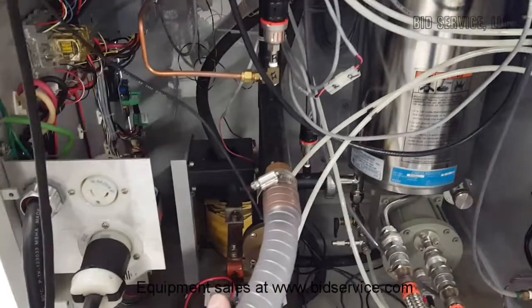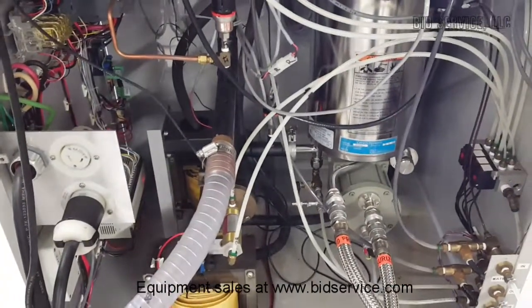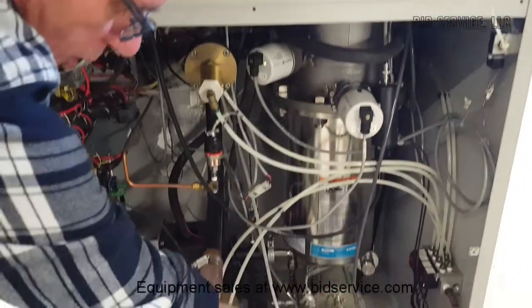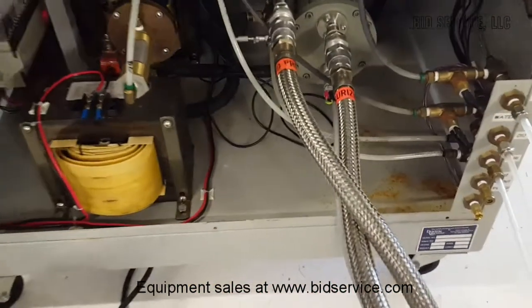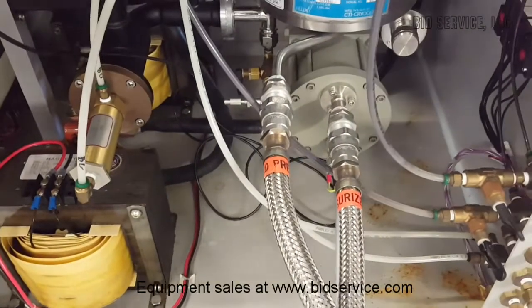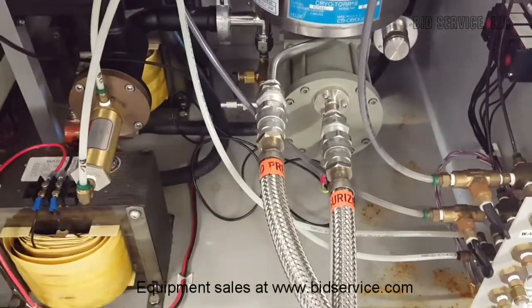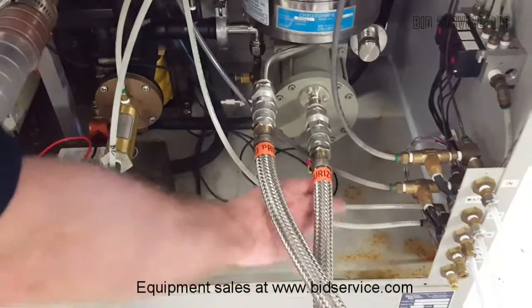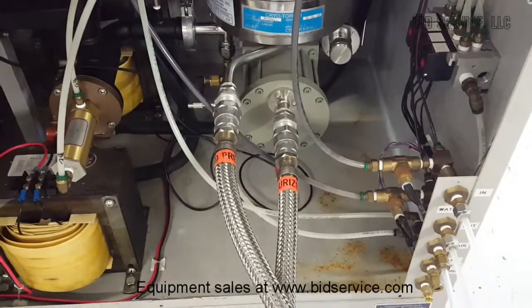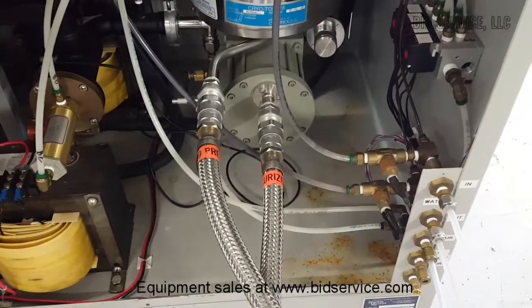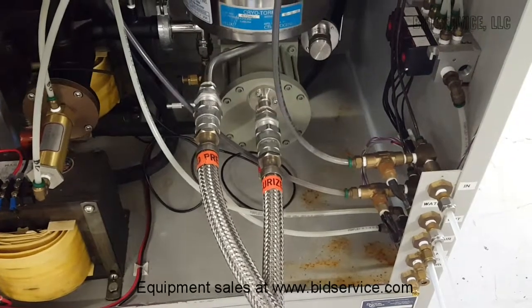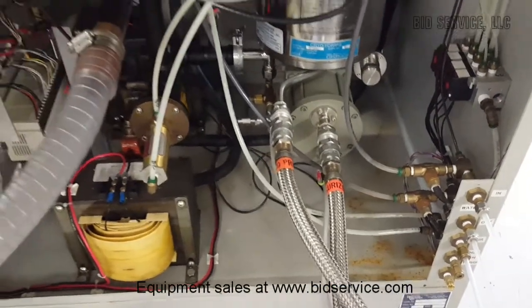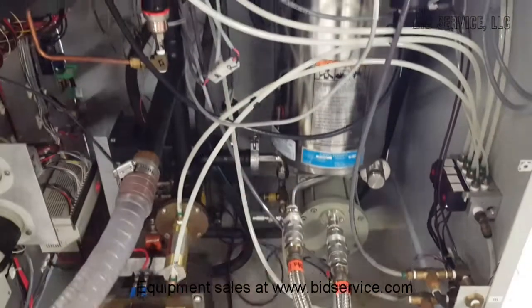You can see here's our vacuum line going to our vacuum pump. There is a back panel. Over here you can see the back panel for the unit. I have it off so I can explain a few things in here. You'll have to connect your cryo lines, and they're marked return and supply to your compressor. And then you have your plug there for the expansion motor. Here's your cryo pump, it's a CTI-8.